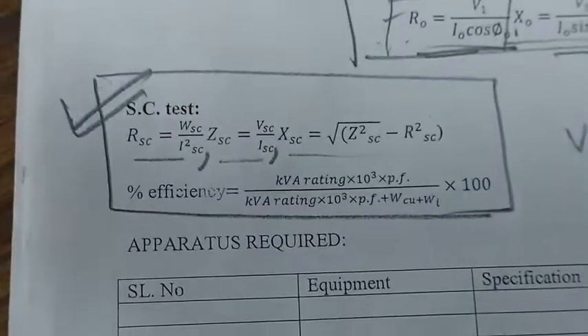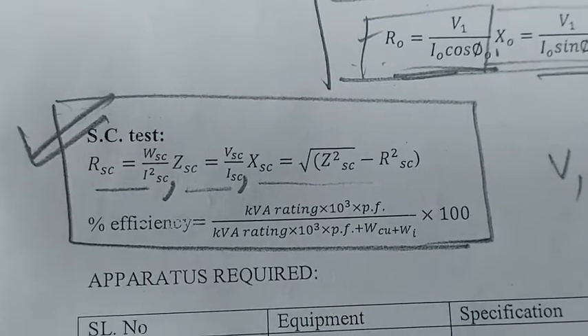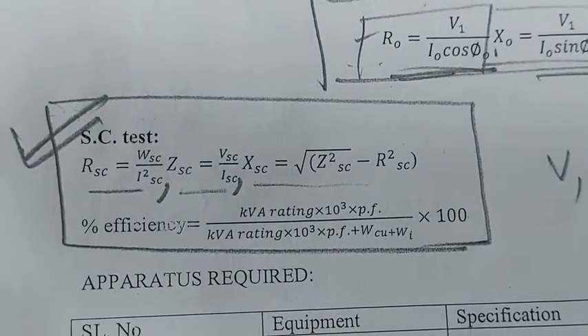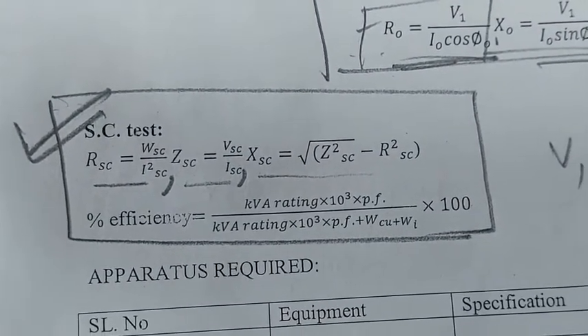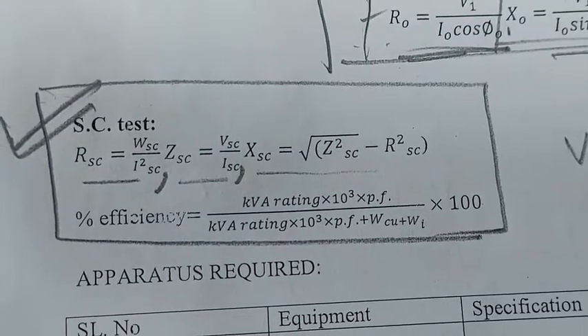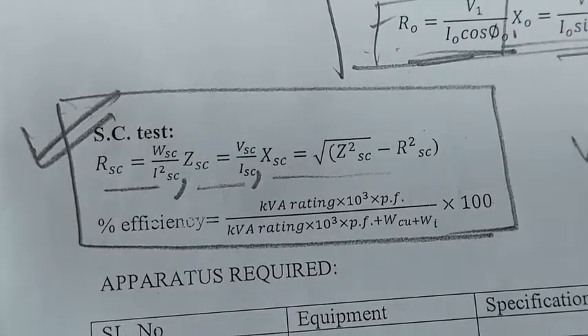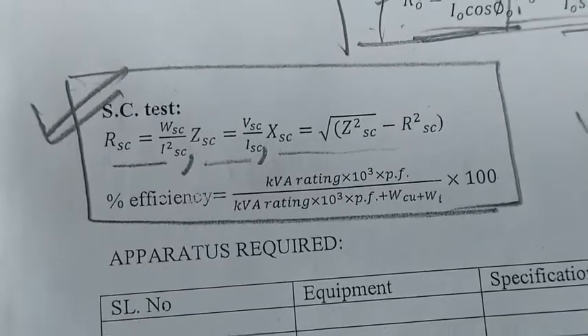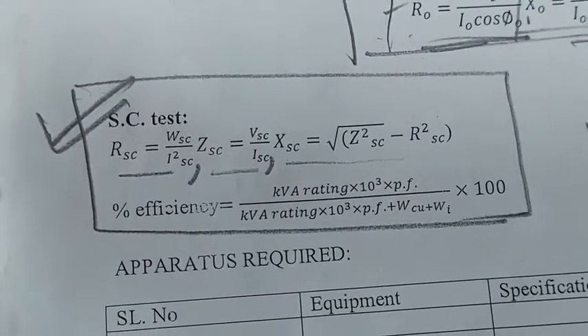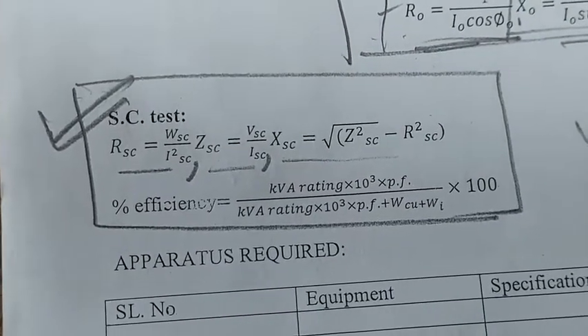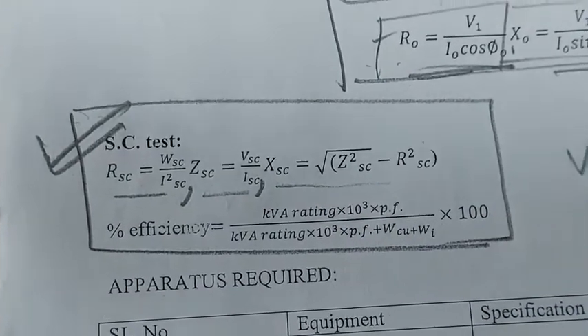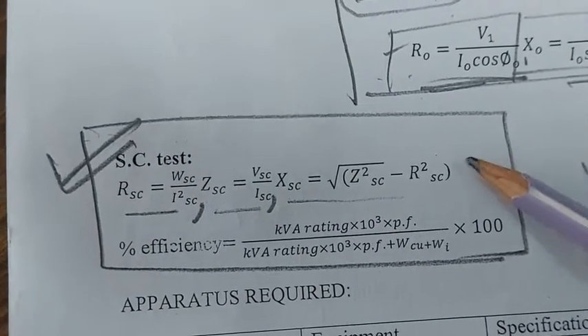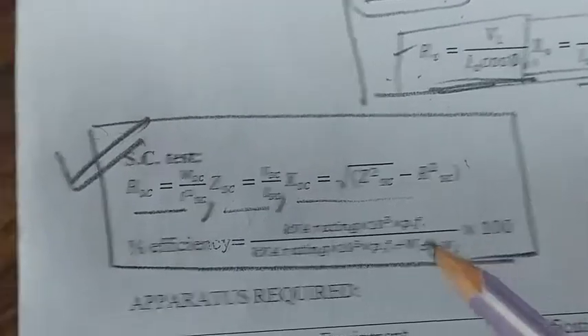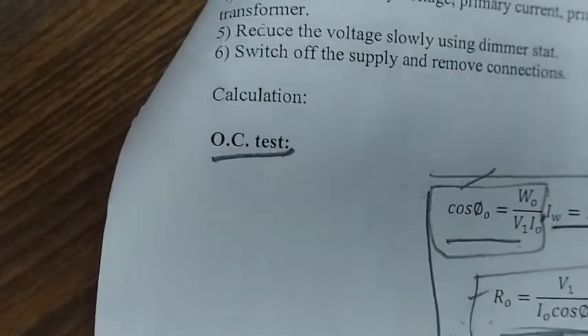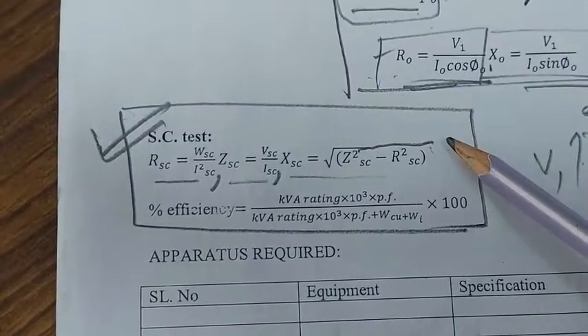and ZSC will be obtained by dividing the voltmeter reading, that is VSC, by the short circuit current value, that is ISC. And once we have ZSC and RSC, we can calculate XSC, that is the reactance part, the equivalent reactance of the transformer in this condition. So it will be the square root of ZSC squared minus RSC squared. The root line will need to be extended a little more, yes. So it will be a little bit more here, yes.